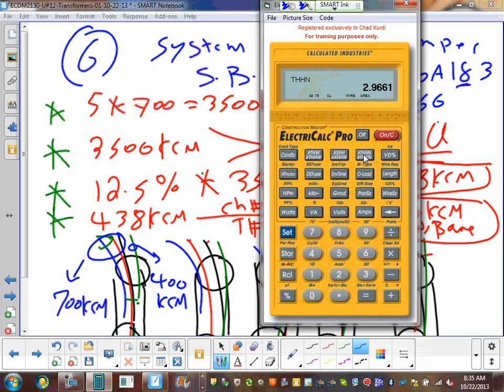I need to add 1 more conductor to it, right? Different size. So here's how we do it in this order. What's the size of the other conductor? 400, 400. Okay, hit K, here's my K, and hit the wire size. Now I told the calculator, please add another 400 kcm copper to the conduit, but I didn't tell it how many of them yet, did I? How many of them are we going to have? One. So you take a one, and you're going to put it in a THHN.